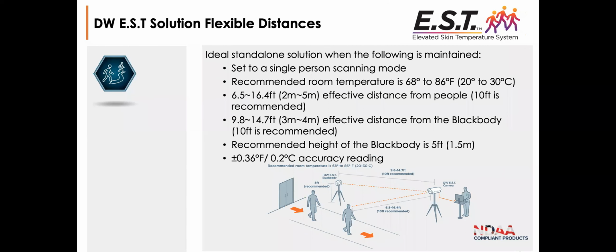As I mentioned, it is very flexible in that it is able to read from a number of distances. We recommend a 10-foot read, but you have between 6.5 and 16 feet of effective distance from the people. Keep in mind, you want to have that black body within the field of view of the camera, and that also we recommend to be about 10 feet, but you have 9.8 to 14 feet of effective distance from the black body itself. We recommend the black body be mounted at about 5 foot, hence the included tripods that come with it.